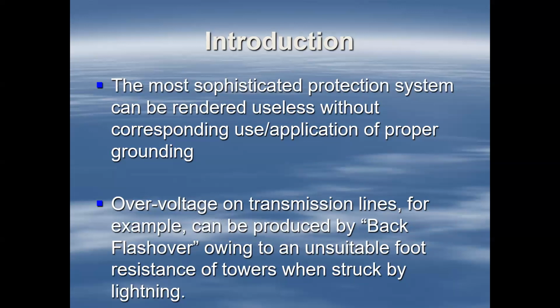But from a transmission distribution standpoint, we can have what we refer to as back flashover. If you have high foot resistance on your tower, and say a lightning strike occurs, because the foot resistance is high, the potential at the foot of your tower will rise. The towers we're talking about are metal towers. That potential can rise to the point where it's much larger than the phase voltage on your system, which results in the back flashover. So it's a very important part of your power system operation.